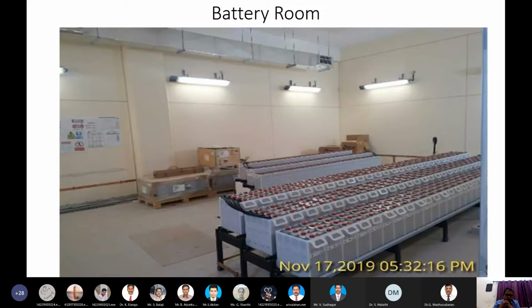What happened was the exhaust fan inside the battery room was not working. If it had been working, the hydrogen exposed during charging might have gone outside. Instead, the exhaust was not on, so hydrogen accumulated in the room, and with static electricity, it blasted. That was one of the remarkable incidents at that substation, and the substation was completely closed.